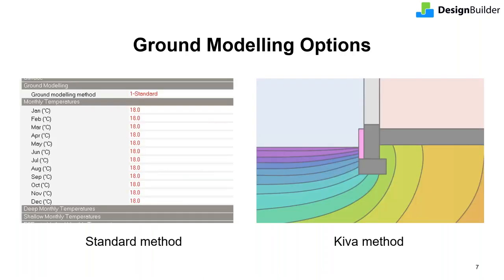There are two main ways to model heat transfers between the ground, the external environment, and the building: the standard method and the Kiva method. The standard method is typically used in all traditional modeling — it uses 12 fixed monthly ground temperatures. The other option, Kiva, uses a multi-dimensional finite heat transfer calculation to determine the ground temperatures and the resultant heat transfers, which is especially needed around foundation and building perimeter. Let's look at each of these in more detail with their modeling setup.